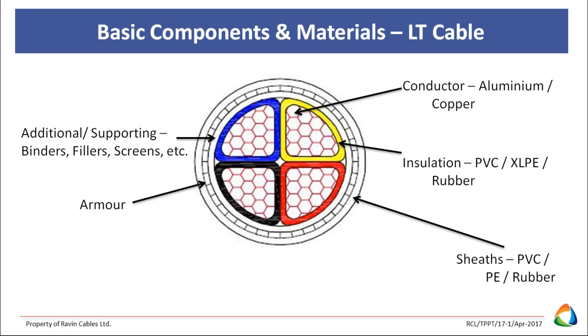Then copper tapes are there. Then fillers, binders are there. Inner sheath is there, armor is there, again sheathing is there. So the basic differences are, one, the conductor shape, and second, the insulation. Here you find insulation all in natural color, but identified with tapes outside the insulation. And here one black layer over the insulation is used, known as a semiconducting layer. This semiconducting layer is at two places, one on the conductor side, and one over the insulation. So conductor screen, insulation screen.